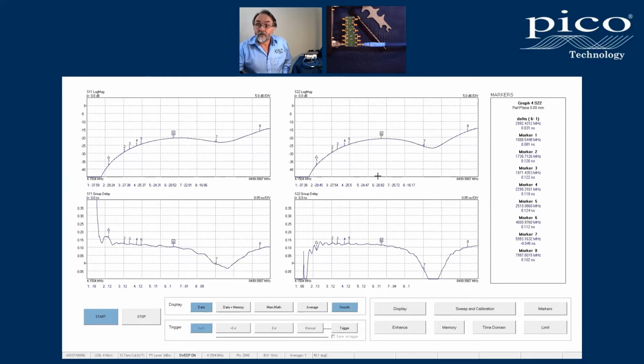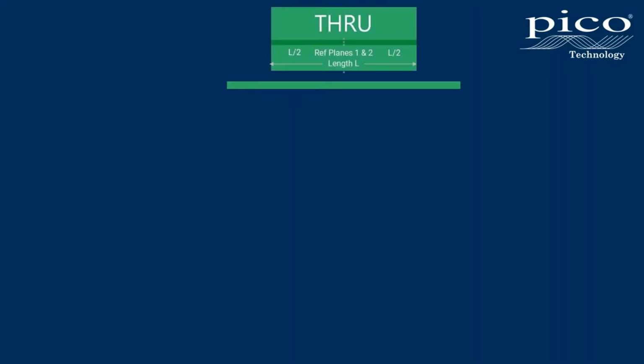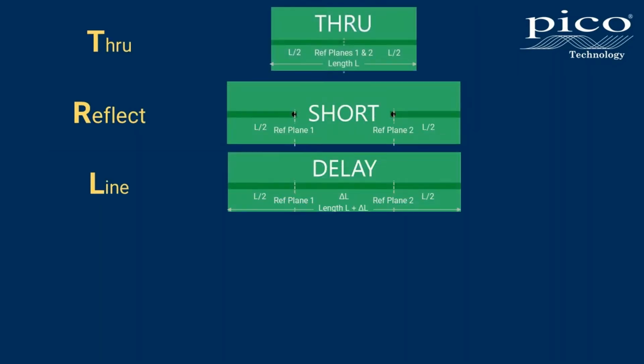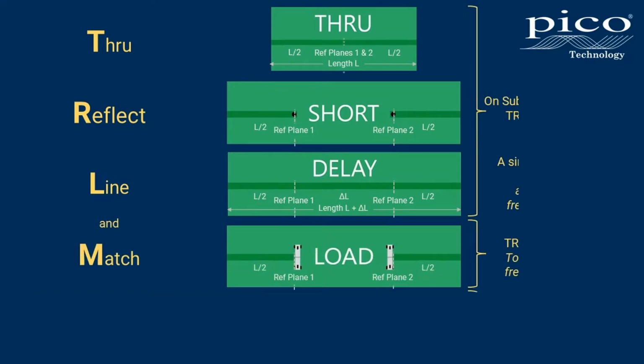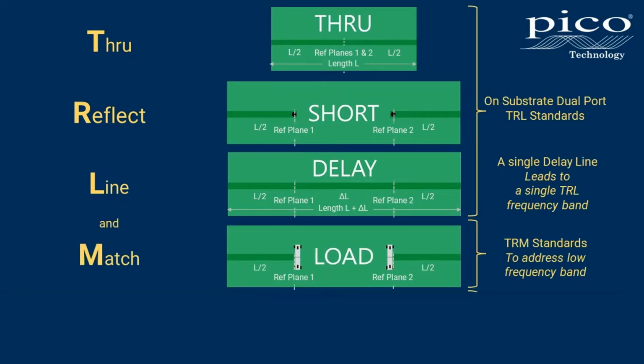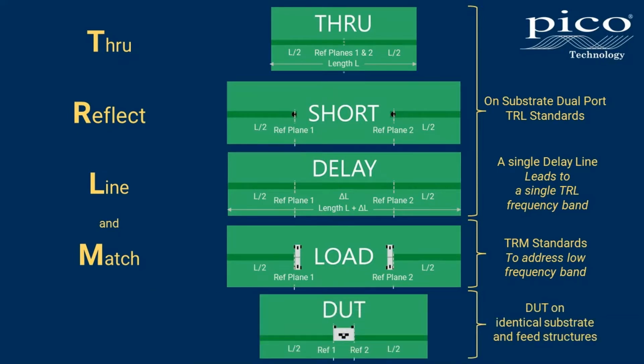Okay, so let's remind ourselves of what we've learned about this board. We have through, reflect and a single line standards. Our single line will define a single high frequency calibration band. And for a low frequency band we have resistive matches. We have all of those calibration standards on the same substrate and on the same feed lines as our DUT.